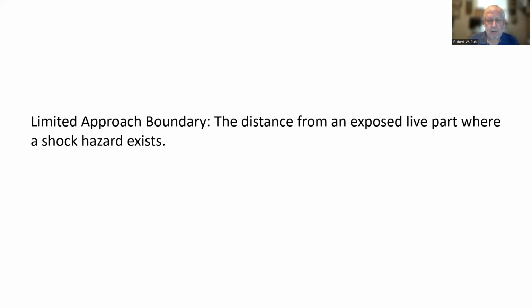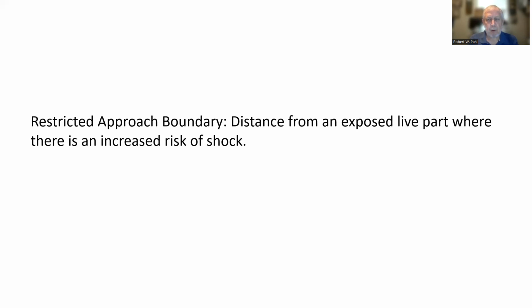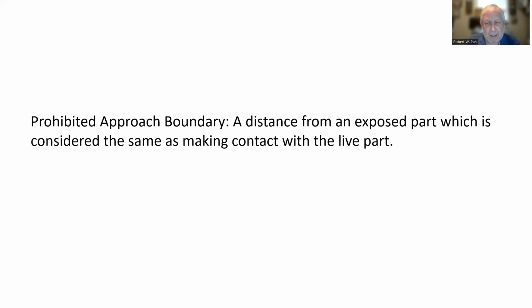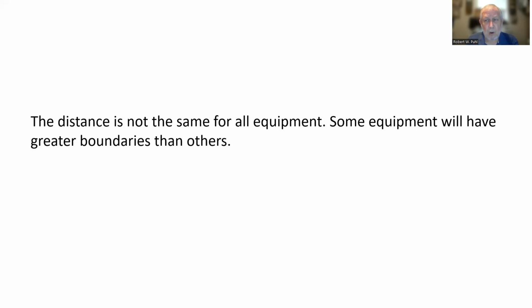Limited approach boundary, the distance from an exposed live part where a shock hazard exists. Restricted approach boundary, distance from an exposed live part where there's an increased risk of shock. And the prohibited approach boundary is a distance from an exposed part which is considered the same as making contact with a live part. So in other words, it's right up close to it. The distance is not the same for all equipment. Some equipment will have greater boundaries than others. That's why when the arc flash analysis or the hazard analysis is done, each piece of equipment gets tagged, and this information will be on the tag, and it'll be different. They can be right next to each other, and they'll have different boundaries and perhaps different PPE.